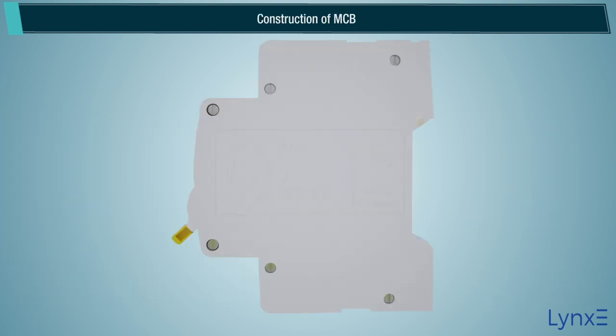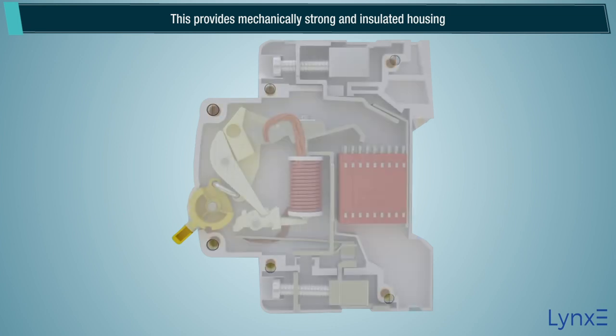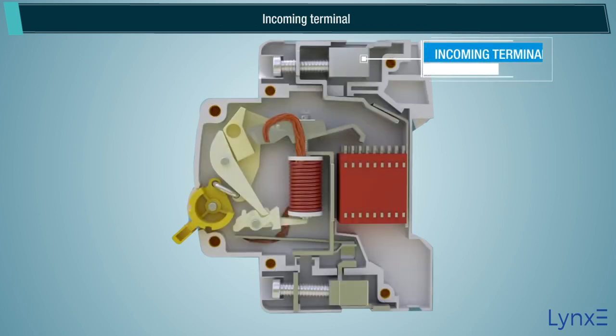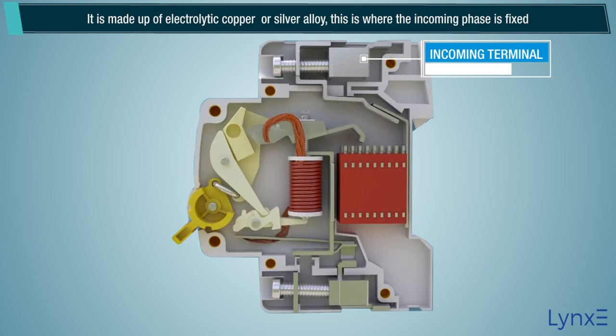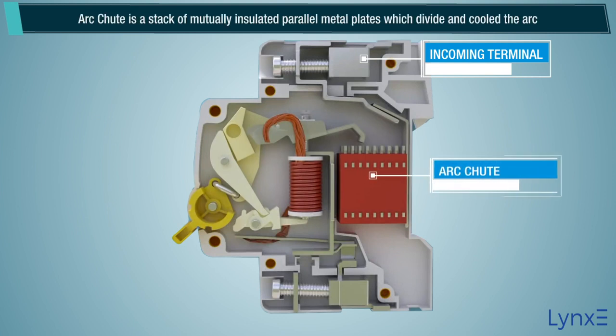Construction of MCB. An MCB embodies a complete enclosure in a molded insulating material. This provides a mechanically strong and insulated housing. Incoming terminal. It is made up of electrolytic copper or silver alloy. This is where the incoming phase is fixed. Arc chute. Arc chute is a stack of mutually insulated parallel metal plates which divide and cool the arc.